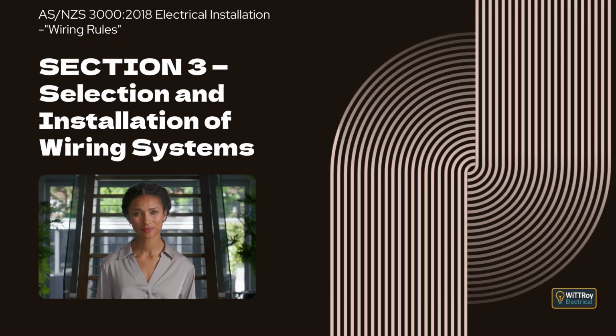Clause 3.13.1 Types of cables. This clause explains that cables supported by a catenary must be stranded cables that provide double insulation, or the equivalent level of insulation. Where installed outdoors, both the cable and the catenary support must be suitable for exposure to direct sunlight. Cables supported by a catenary are considered to be adequately supported because the catenary carries the mechanical load. Clause 3.13.2 Catenary supports.